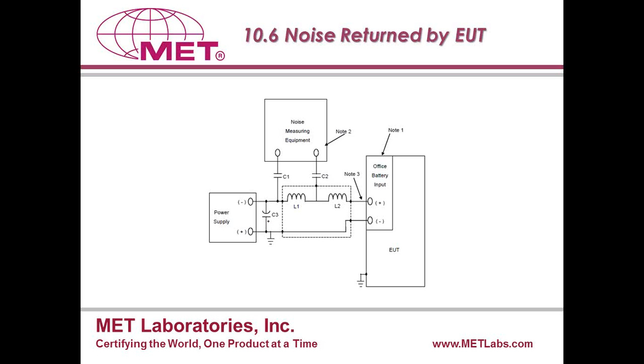Now, with this requirement being added to 1089, with the switching of the references to ATIS instead of T1.315, there has been ambiguity based on the standard whether labs should go back to 1 megaohm, as was the common practice in the industry in the past, or go with the 50 ohm system. So some labs went with 1 megaohm, some labs were using a 50 ohm spectrum analyzer. Long story short, you will get different results depending upon the input impedance of your instrumentation. In my opinion, with the release of issue 6, they tried to clarify that ambiguity so that everybody is doing the testing for noise in a consistent manner and results are repeatable if one goes from one lab to the other.